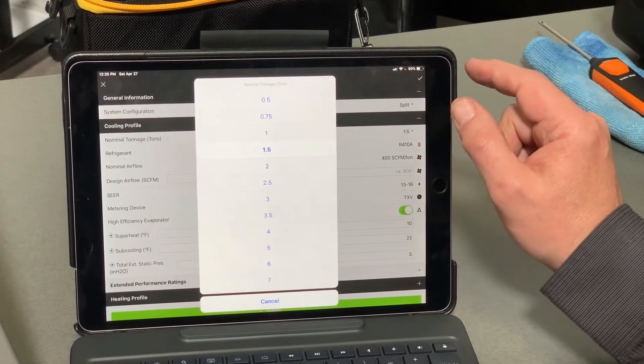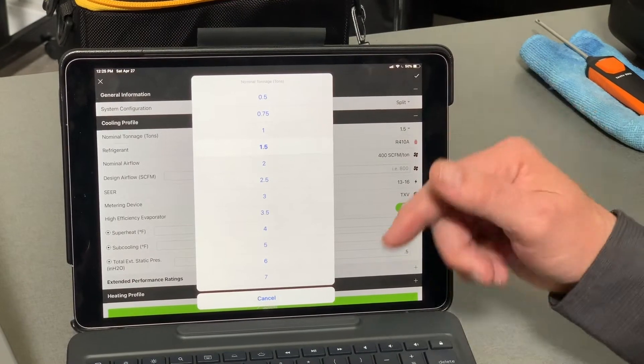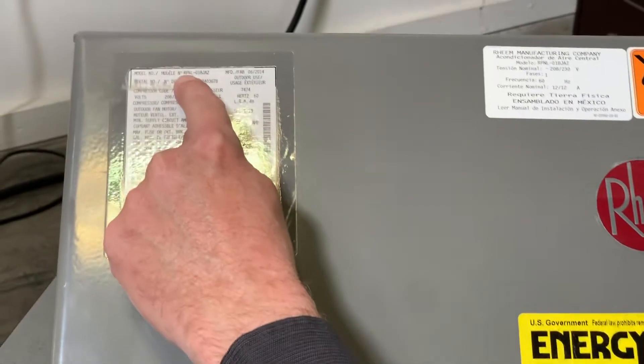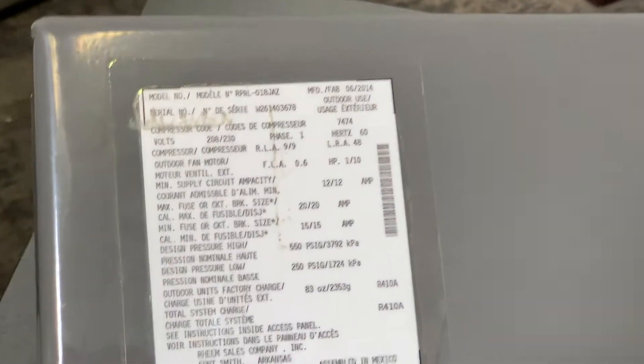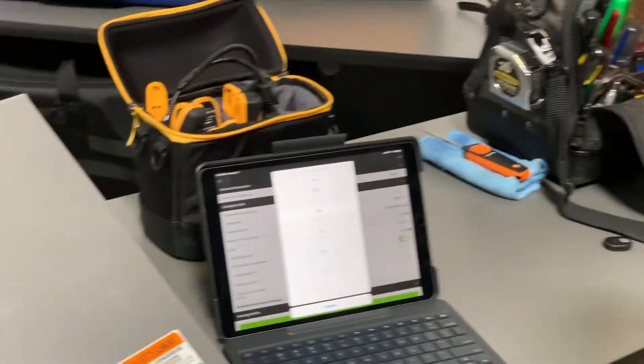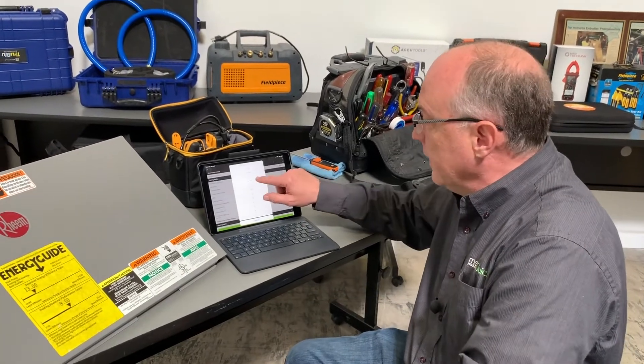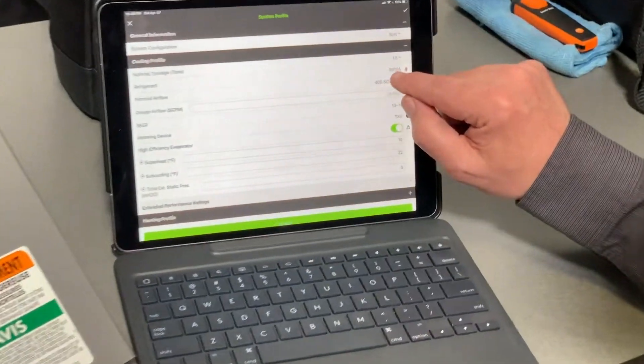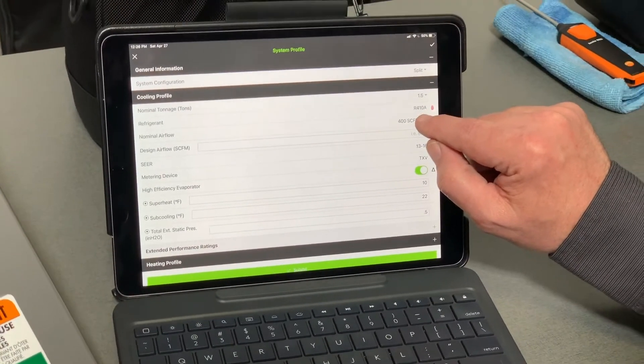Number one, I tell it the tonnage. In this case it's a ton-and-a-half system. If you look at the label, this is an RPNL018 — the 018 means 18,000 BTUs, and at 12,000 BTUs per ton, that's a ton and a half of cooling. So I'll select ton and a half. The refrigerant on here is R-410A — you're going to find that on the manufacturer's label as well.